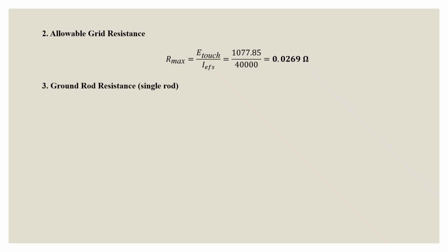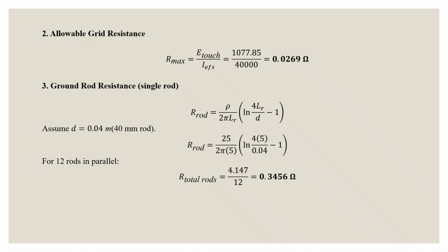So next we will calculate allowable grid resistance, which is R max. We have the formula E touch upon the I EFS, where I EFS is leakage current or short circuit current. We have the values from the given data, and by calculation we got the R max value to be 0.0269 ohms. Then we'll calculate ground rod resistance for a single rod, for which we have this formula, and we assume D equals 0.04 meters, which is nearly a 40 mm rod. So substituting this value of D in the equation, we got this equation. And for 12 rods in parallel, we calculated the resistance to be 0.3456 ohm.